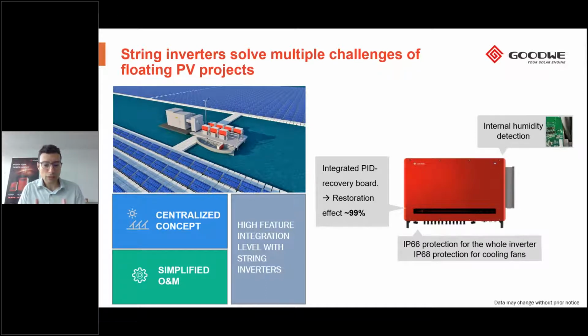Still, and this is maybe a bit of a misconception, IP rating is critical, but it's not sufficient for this type of application, because what IP rating doesn't say is how humidity impacts in the long run. IP rating doesn't detect whether humidity will diffuse slowly inside the inverter over the years, and that's something which might happen. To counter that, we are the only manufacturer who has implemented internal humidity detection sensors inside the inverter, which means after many years under these very strong humidity conditions, in case, despite the best product design, humidity is accessing the electric components, the humidity sensor will give an alert, and the operator of the power plant will be able to react before any damage happens.